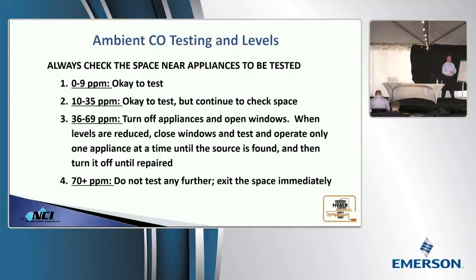Anything over 70 parts per million. At that point in time, you need to leave. You need to evacuate. Don't go in the house. Don't be a hero. Turn the equipment off. Open anything that you can. Turn the gas meter off if you have to, or the propane tank. Get the customers out. You may need to call 911 at this point, depending on if anybody's showing any types of symptoms or anything. But before you do any type of testing, this is what you need to do.